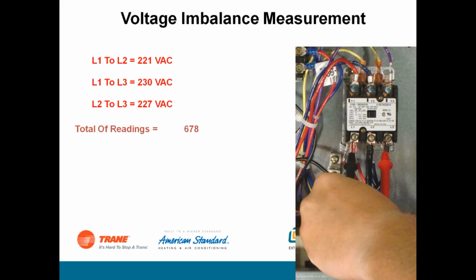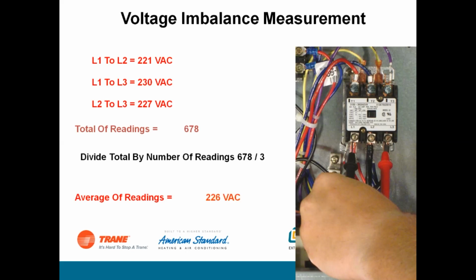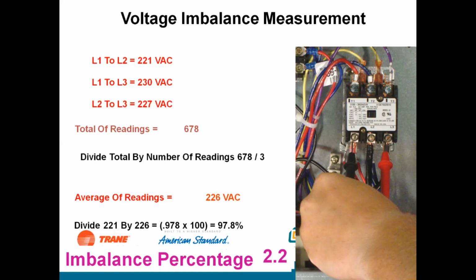What you do is you add up the voltage of all three and divide by 3, which gives you an average voltage of, in this case, 226 volts. Then you take the voltage that's the farthest away from the average, in this case 221 volts, and do the math. Divide 221 by 226, and what you get in this case is 97.8%, or 2.2% imbalance. You're allowed a 2% imbalance on three-phase equipment. So at 2.2, that's out of spec, and that could be an issue. Well, actually, it is an issue. You have to be careful with that. 2.2 doesn't seem like much, but it's enough to cause problems with the system.